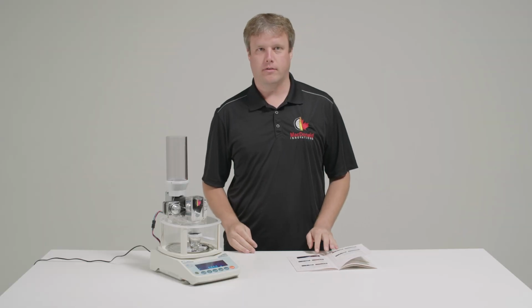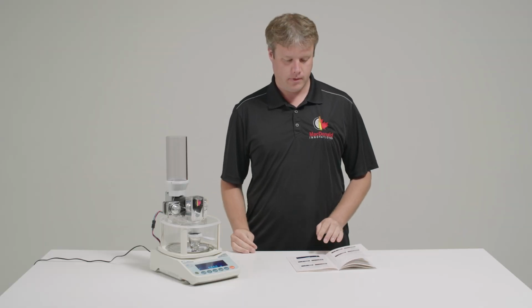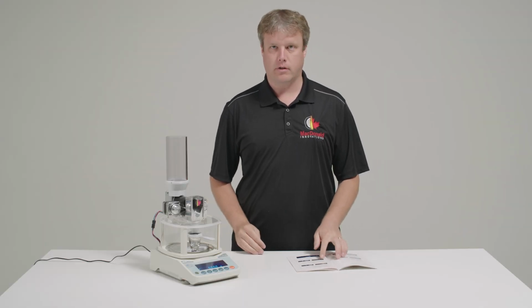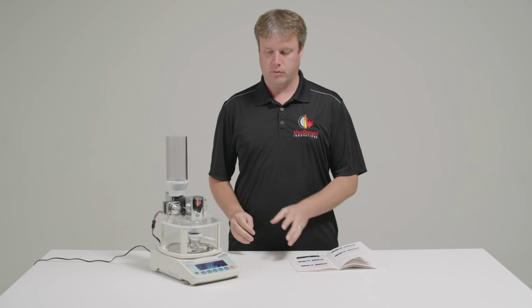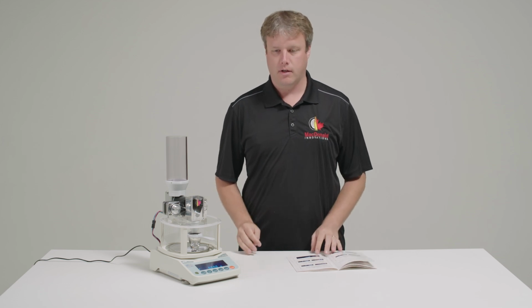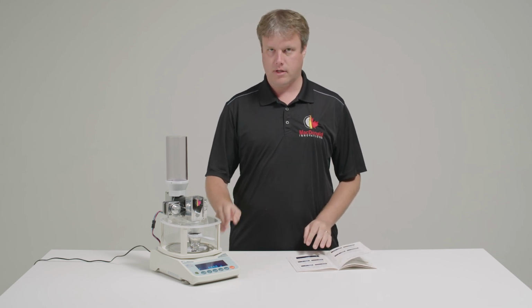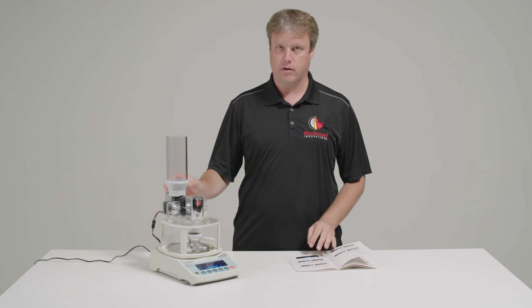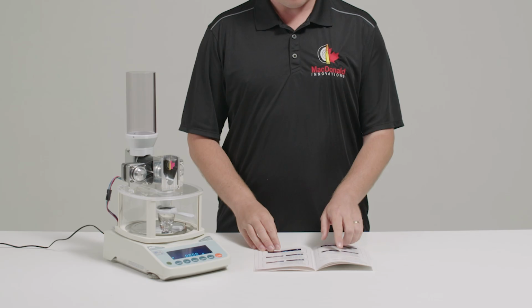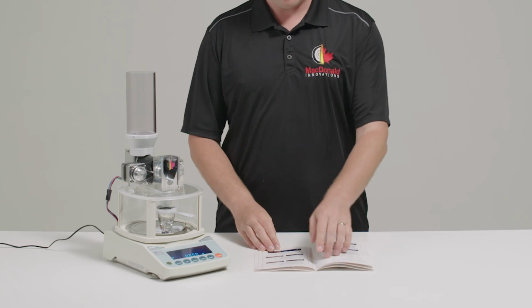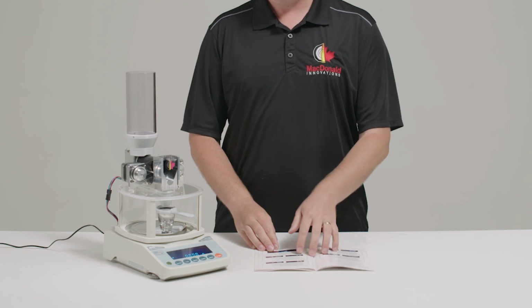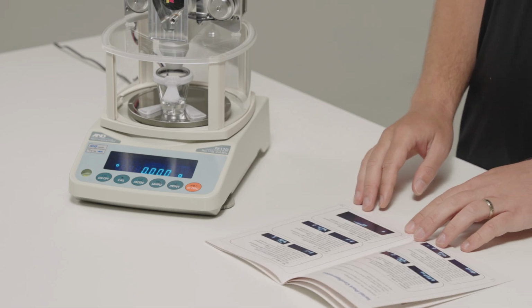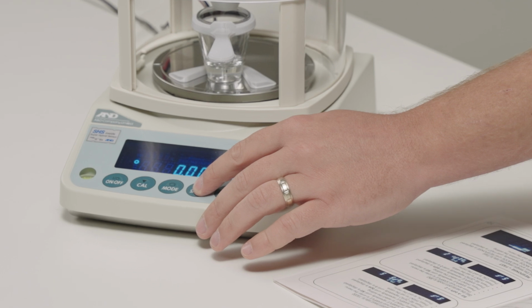Next, we're ready to configure the scale serial port. So these are settings that we're going to configure in the scale, which will stay permanently set in the scale, and they control how the scale sends its weight data to the AutoTrickler to allow it to work. But you should follow the manual. The first 4 sections are very similar. We'll just go into the appropriate menu and set the settings step by step as it explains in the manual.